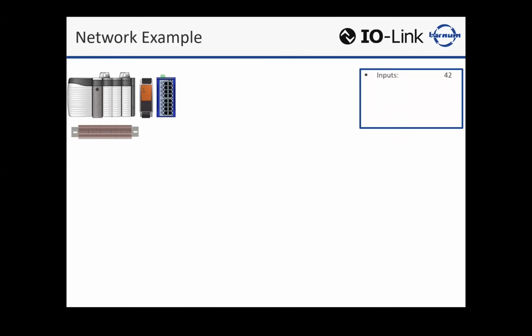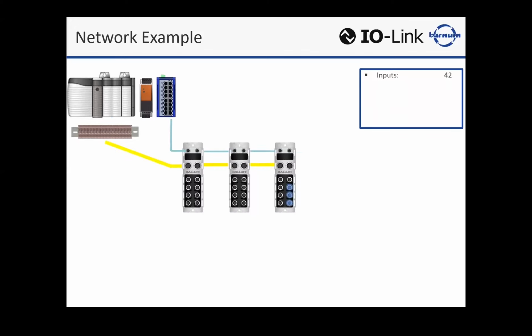All right, perfect. So we go back to those same 42 inputs. Yep. Those will be through some field IO blocks. Yeah, typically a 16 IO configurable block. So in this case, we put three, and for the sake of argument, say they're Ethernet IP blocks. Okay. 16 IO configurable. So obviously, that gives us a total of 48 inputs. We're only using 42, six spares left over. Perfect. And then we'll add the same for the outputs. Yep. Still have an output block. So we're more than likely going to have that dedicated, because we can run a separate aux power run to it. And that'll handle 16 outputs. And that covers our needs.